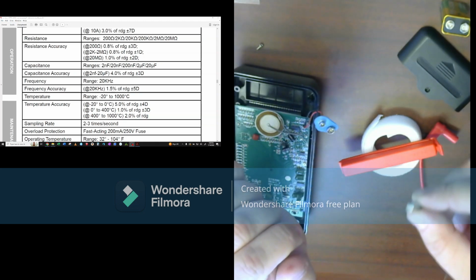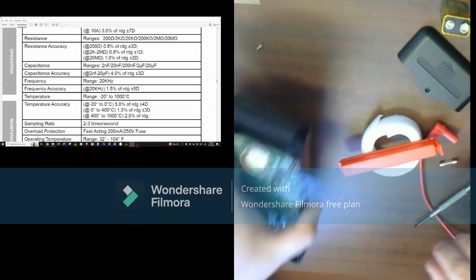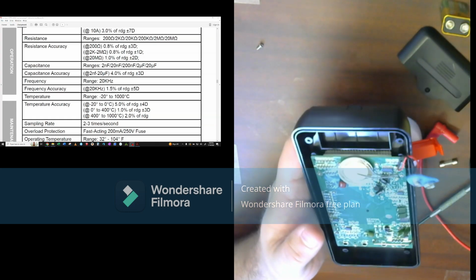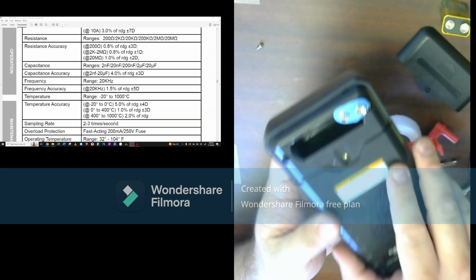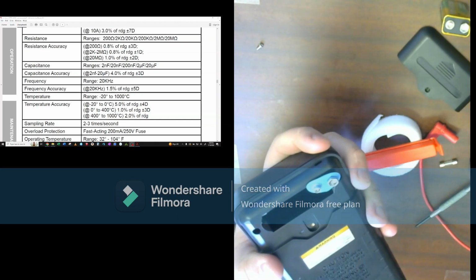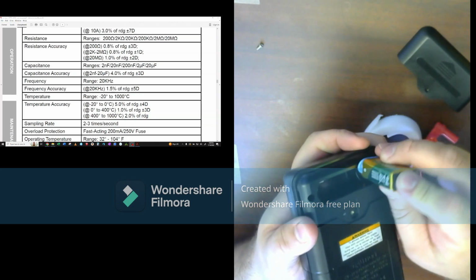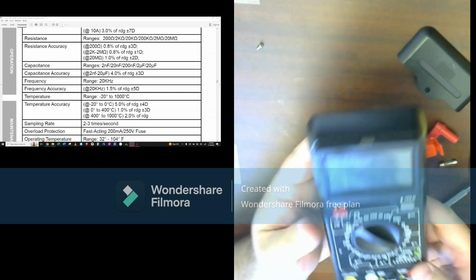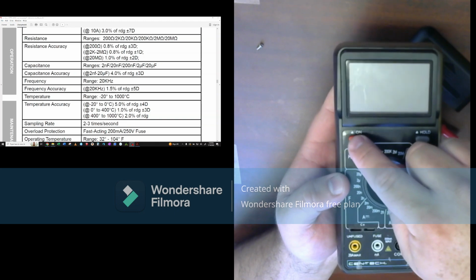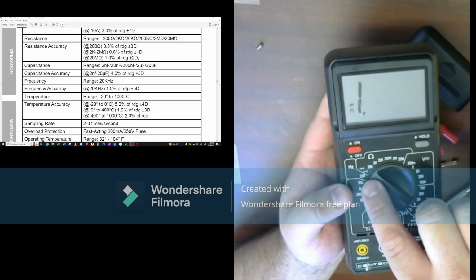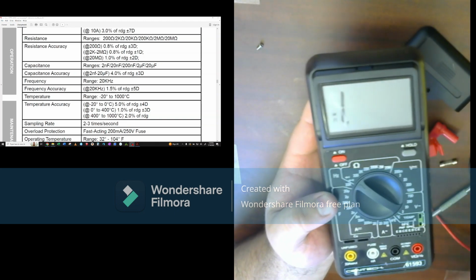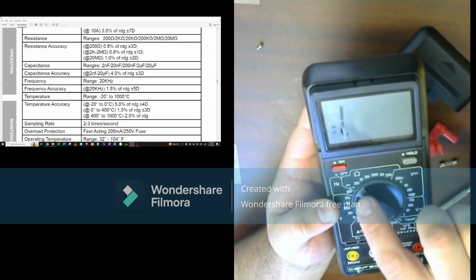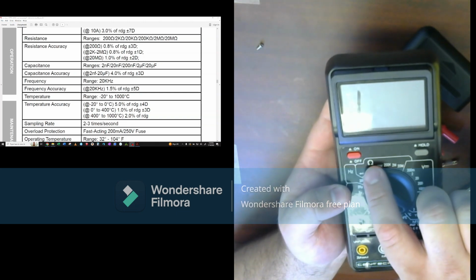So we've got the fuse taken out. We're going to set that off to the side. We're going to take our cover, put the battery compartment back through like this and just put it together. We're going to hold on to it. I'm not going to put any screws in. Take my battery, match up the sides again, it'll only fit one way. Pop that back in. Now when we flip it over, we can turn this on, and we set this little thing to continuity. So now, when we're trying to measure continuity, this is under our resistance, the ohms measurement.